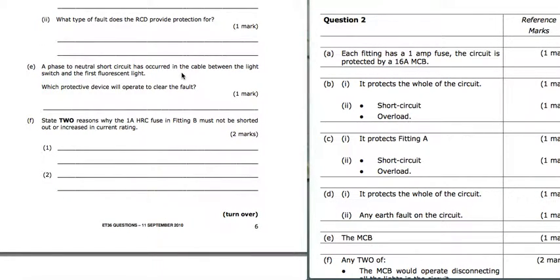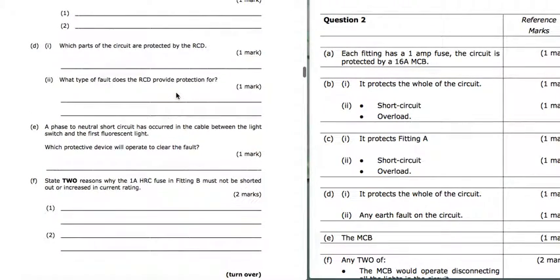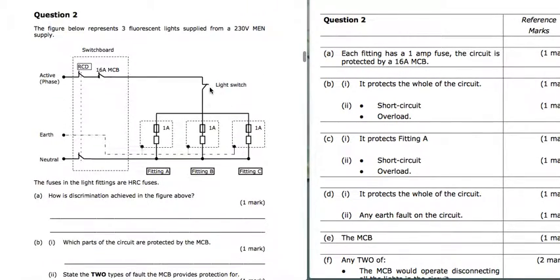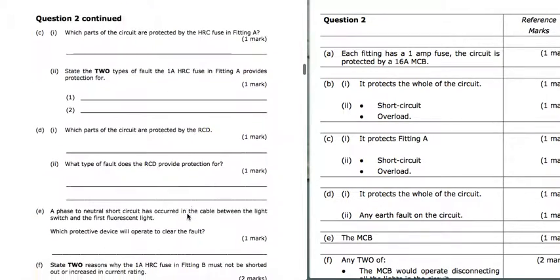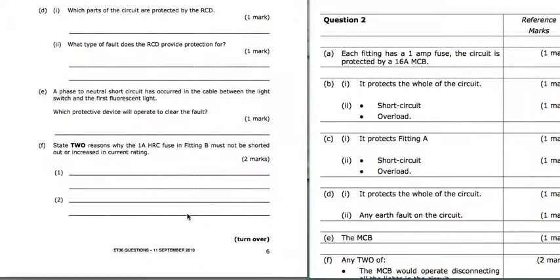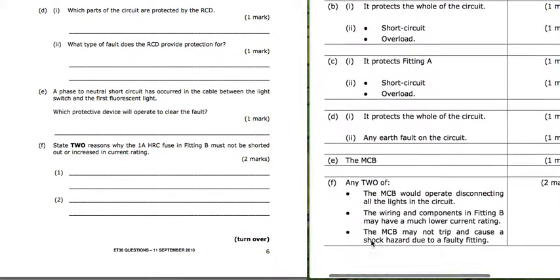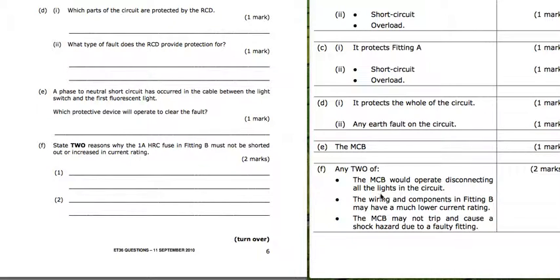Phase to neutral short circuit has occurred in the cable between the light switch and the first fluorescent light. Which protective device will operate to clear the fault? So if we've got one between the light switch and the first fluorescent, there's the light switch there and the first fluorescent is in there somewhere, then the MCB is going to protect it. State 2 reasons why the 1 amp HRC fuse in fitting B must not be shorted out or increased in rating. So the MCB would operate disconnecting all the lights in the circuit.